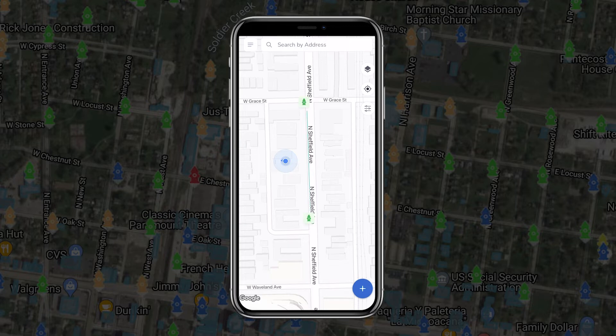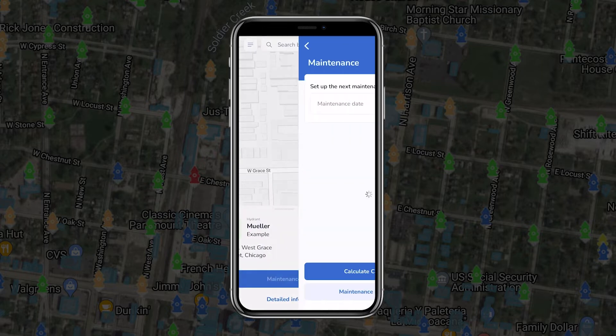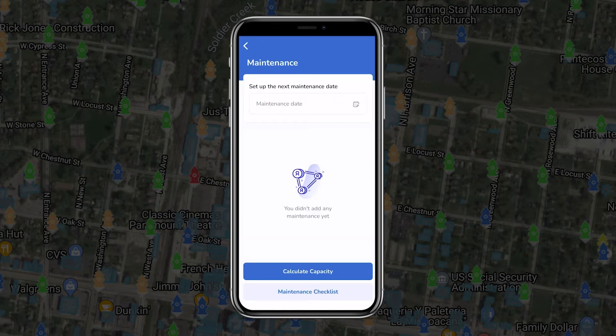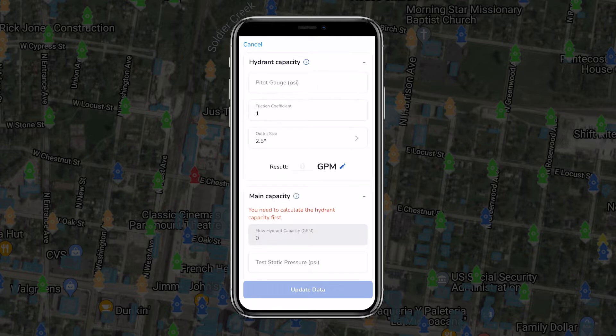The app will allow you to calculate hydrant capacity as well as main capacity by selecting your test hydrant, tapping maintenance, and tapping calculate capacity. Hydrant capacity is calculated using Bernoulli's formula, whereas main capacity is calculated using the Hazen-Williams formula.